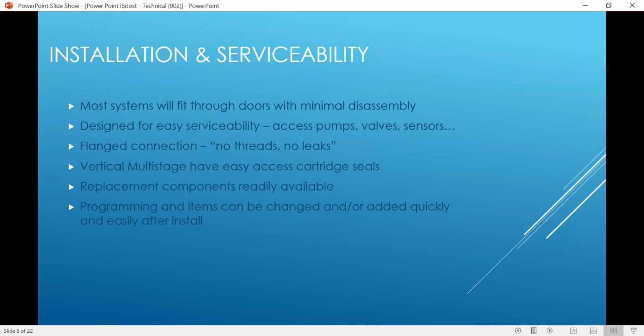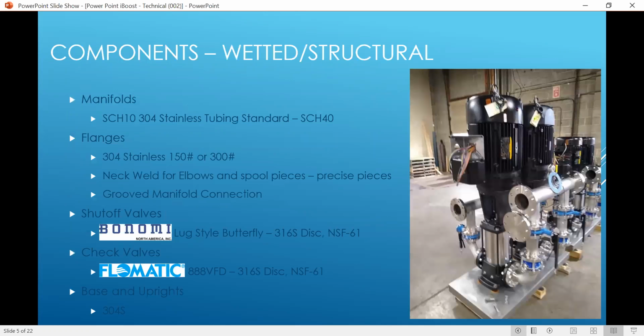As far as the pumps, our vertical multi-stages all have cartridge seal replacements, and let me see if I can go back to that photo there. I can show you. So you've got your cartridge seal right in here in this section, and those are really easy to change. You don't have to remove the motor to change a cartridge seal. We can get you the parts fairly quickly. We stock most of that in our warehouse, and you can also get them from a local supplier if you needed. But your vertical multi-stage pumps are obviously for your high rises that are probably over 10 stories.